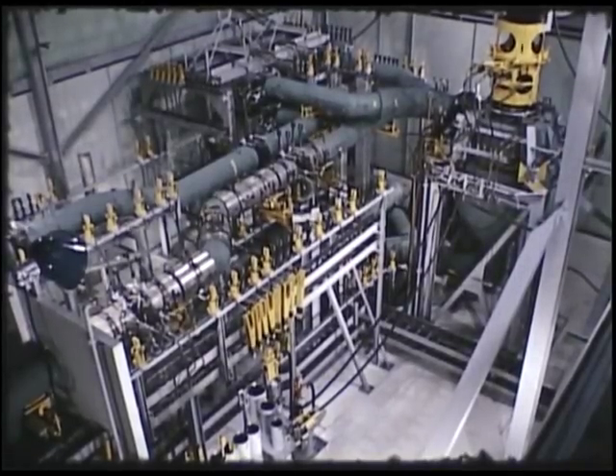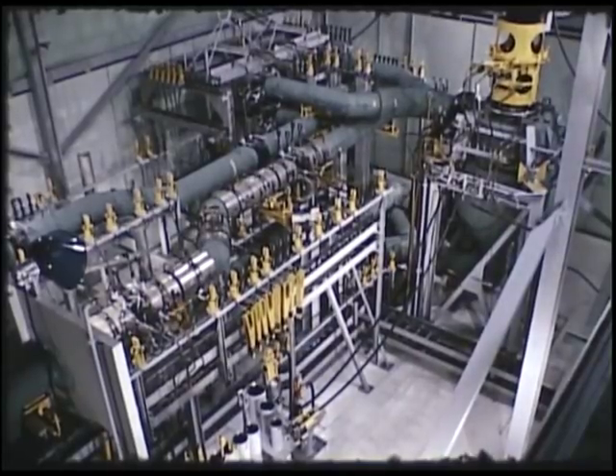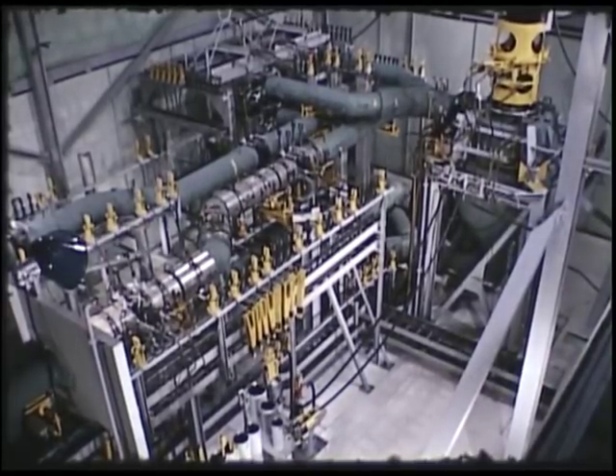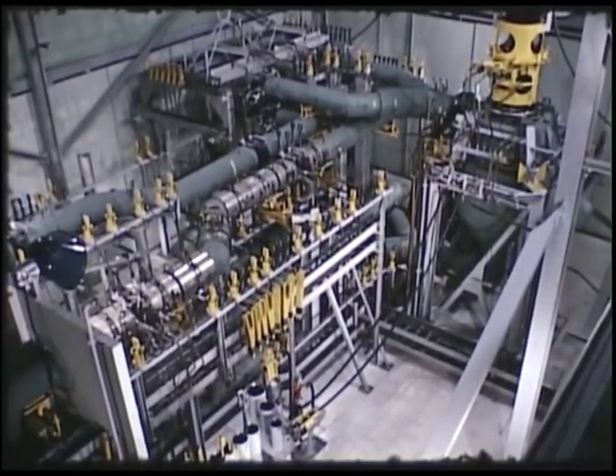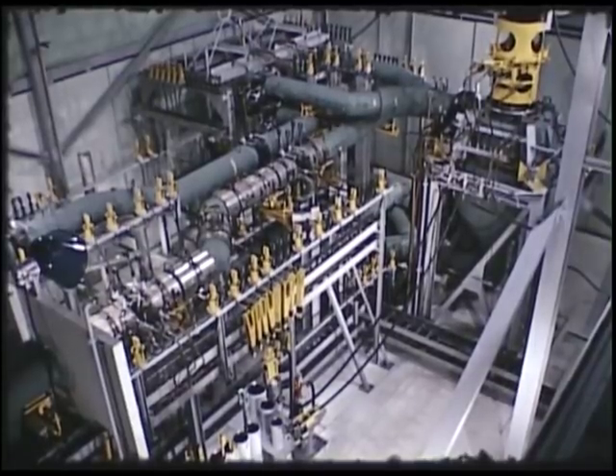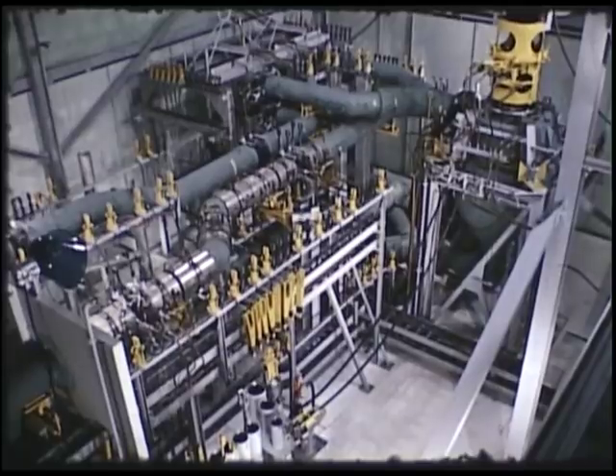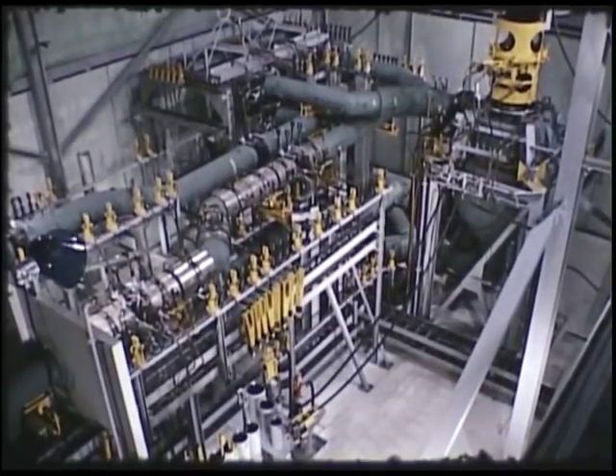This facility is a mock-up of a small reactor system, approximately 20 thermal megawatts in size. A simulated fuel mixture of sodium fluoride, zirconium fluoride, and uranium fluoride was circulated through the loop at 1,200 degrees Fahrenheit and at 5 pounds per square inch helium blanket pressure.